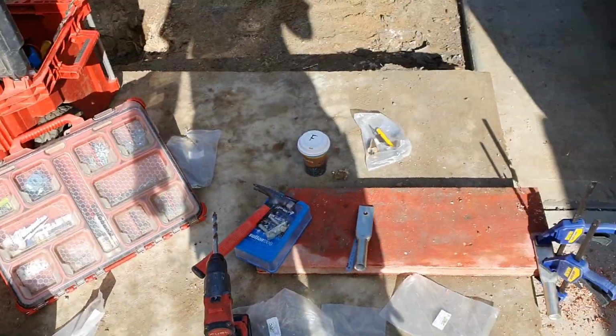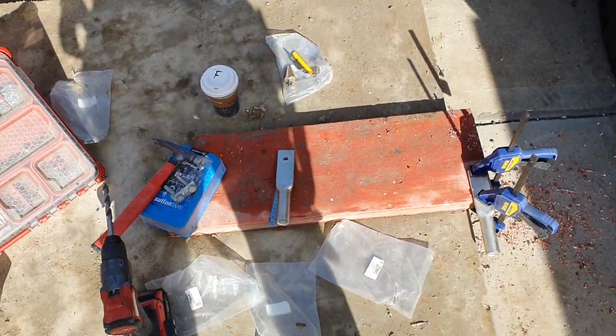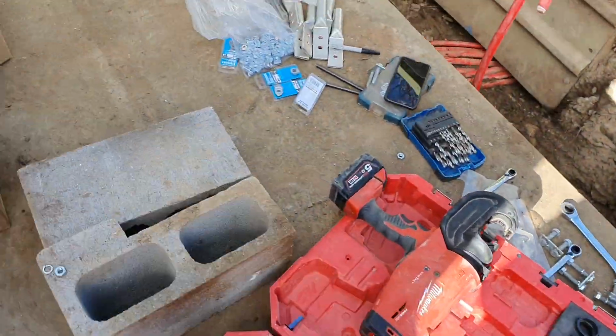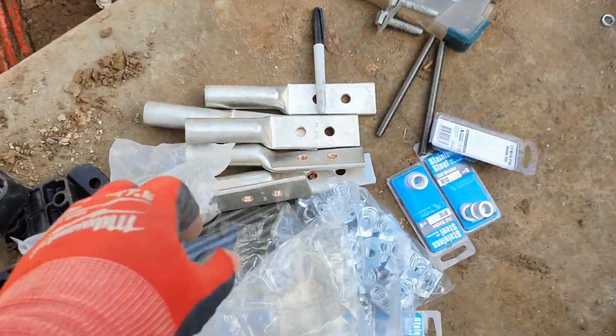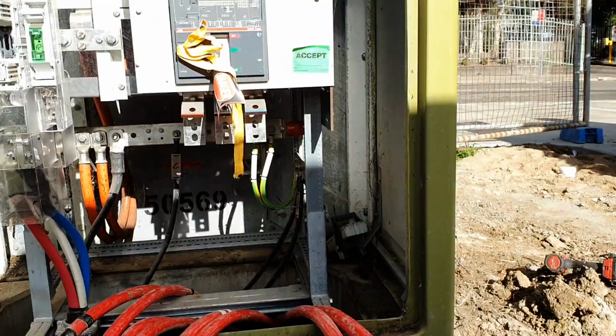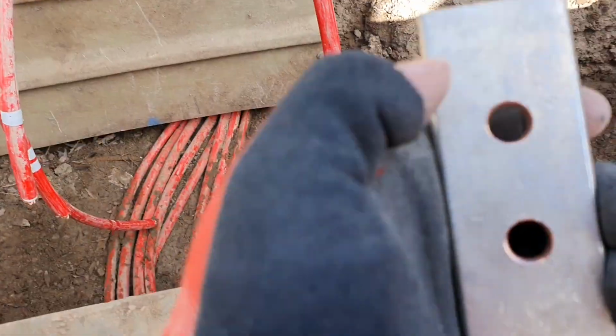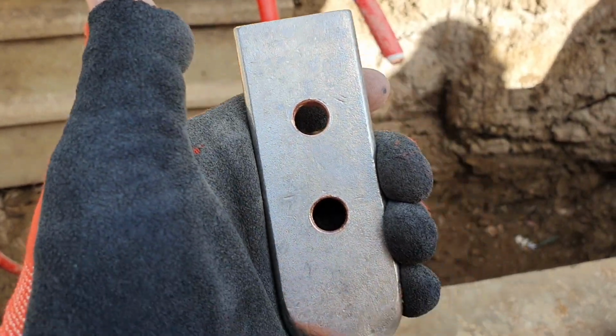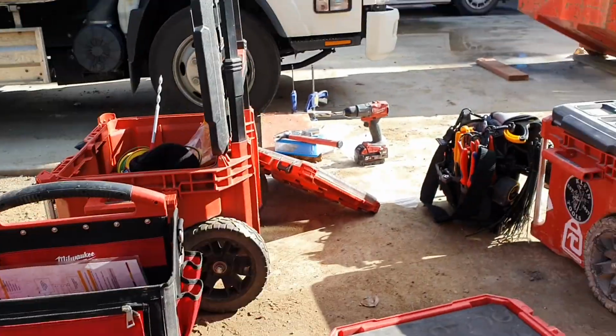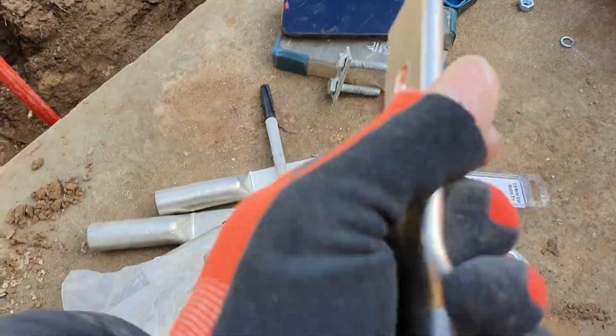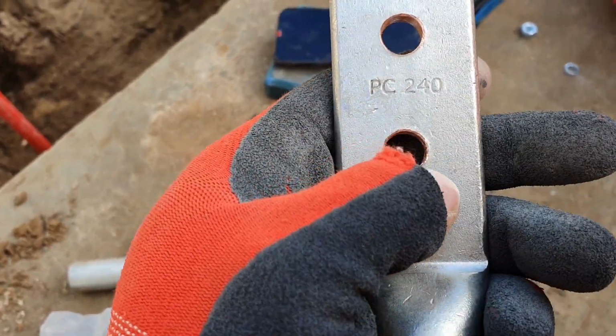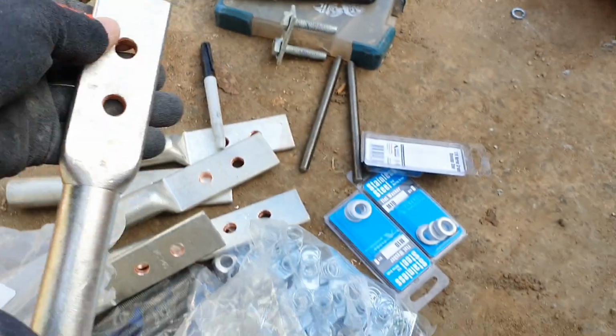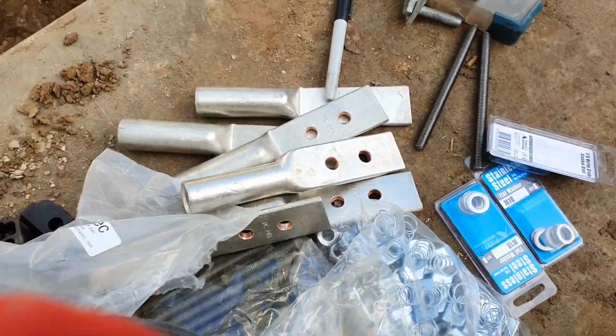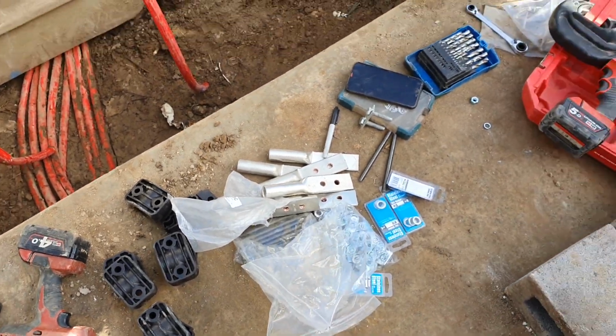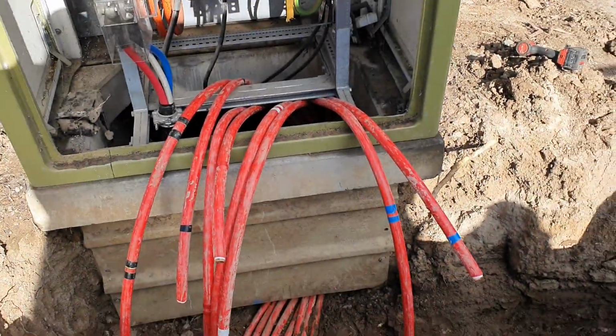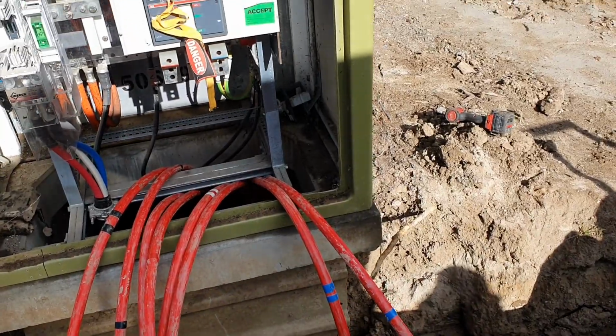We've got all the gear out on site here, drilling the lugs. Got these all drilled out so they're double studs to suit the bottom of that breaker, about 32-33 mil spacing. Drilling them on the pad with the clamps because copper is horrible and grabs real bad, then I've reamed it to smooth them up. It gets really hot when you drill it too, since copper work hardens - just something to be aware of.